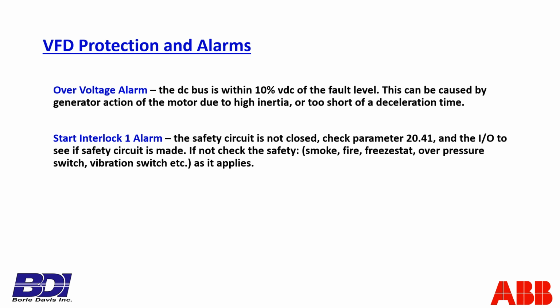Now, if that's the case, that rotor is going to turn that motor into a generator, and it'll generate energy into the drive, and that generated voltage will attempt to and will charge up the DC bus. And the capacitors in the DC bus are the limiting component that is subject to voltage stress. And hence we have to shut the drive down.